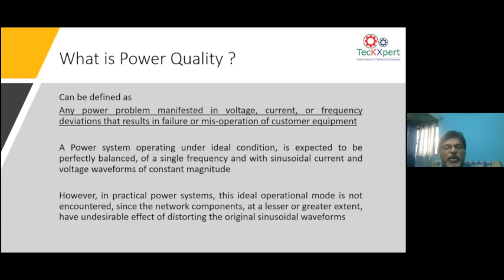Now, what is power quality? As we all know, when power is generated in a generating station, we have a perfect voltage and a perfect frequency, 50 hertz, and the generation voltage also has a fixed magnitude. So you have a perfect sine wave. But when this power is transmitted through the grid, the grid has its own effect on the power being transferred. So ultimately the waveforms, whether the voltage or the current waveform, get distorted.